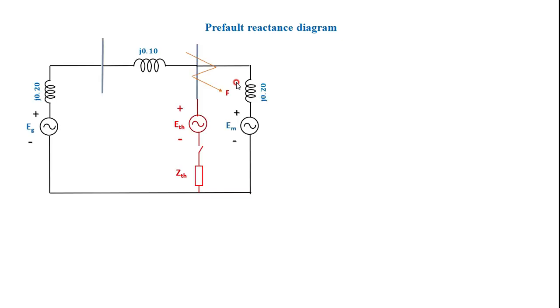Drawing the pre-fault reactance diagram: the generator has subtransient reactance of 0.20, the line has 0.10, and the motor has 0.20. The fault is occurring at the motor terminals. Our objective is to find the Thevenin equivalent seen from the fault point. The Thevenin open-circuit voltage equals the pre-fault voltage Vf, and we also need to find the Thevenin equivalent impedance seen from these two terminals.